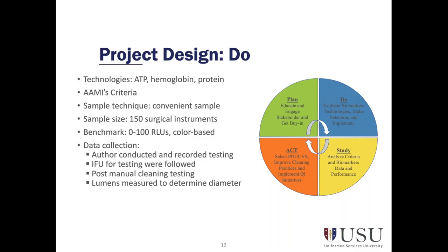Now, there was a special focus on instruments that were not able to sustain mechanical cleaning. You can imagine why that is, but I will talk a little bit more about that later in the presentation. I utilized the benchmark recommended by the manufacturers' IFUs to protect the integrity of the testing procedures. I performed all the 150 tests. All the tests, which were broken down into 50 per system, were completed after manual decontamination. All instruments were considered clean through visual inspection before testing.